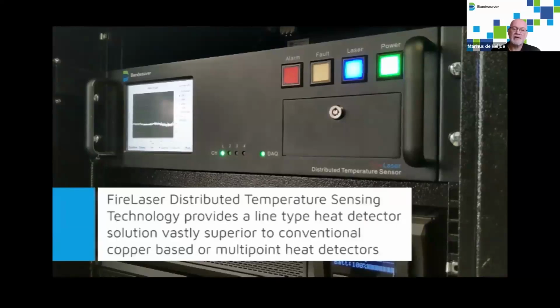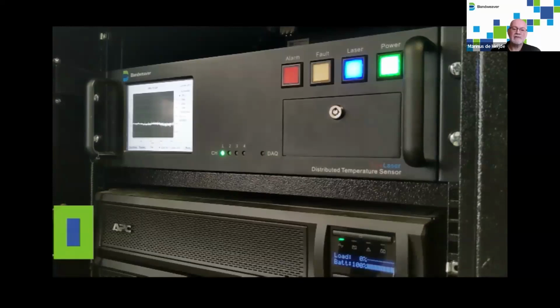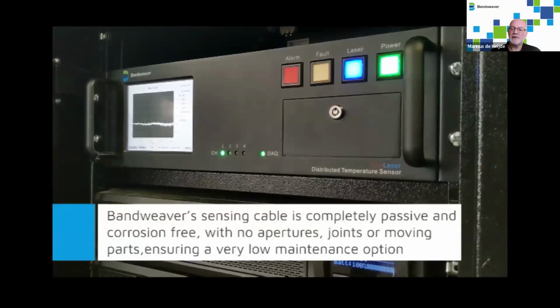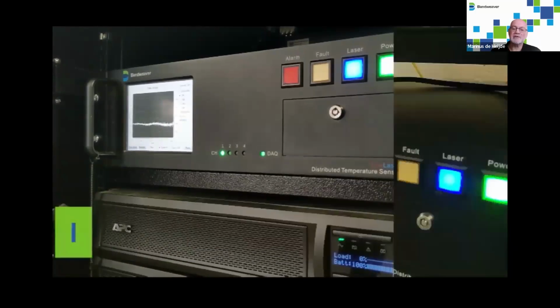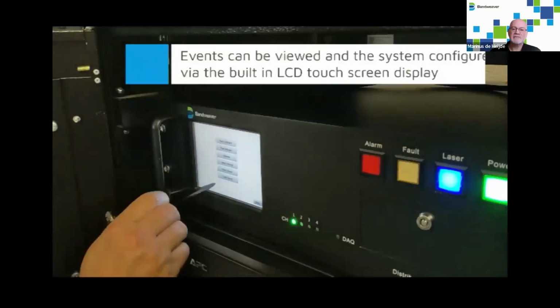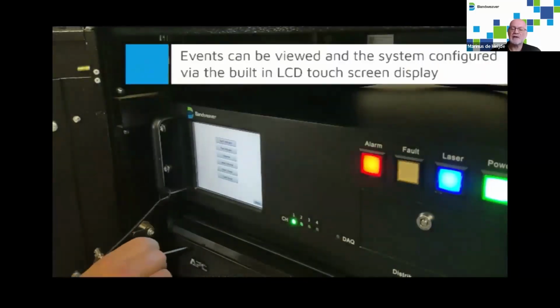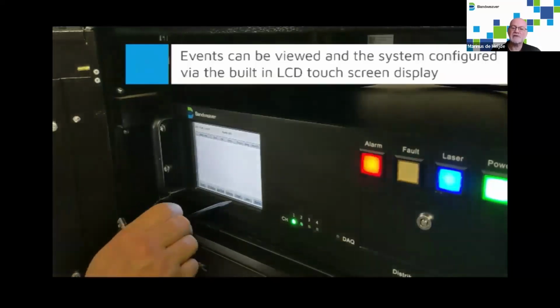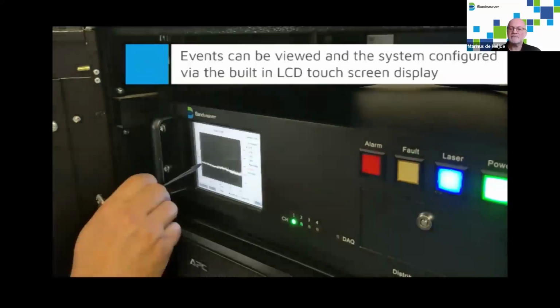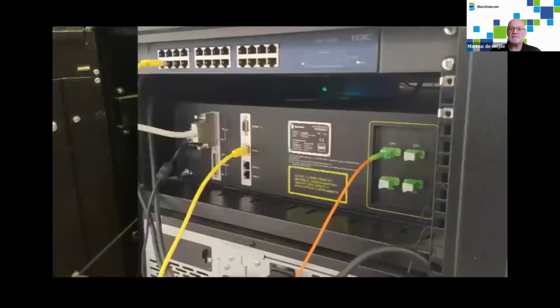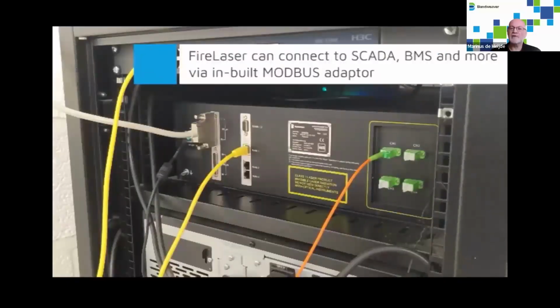This is the front of the unit, where you have an LCD screen so you can program the unit. It's completely passive, the cable, as I already mentioned. No apertures, joints, or moving parts. Events can be viewed and the system configured by the built-in LCD touchscreen display. At the back of the unit, we can connect to SCADA and building management systems via the built-in Modbus adapter.